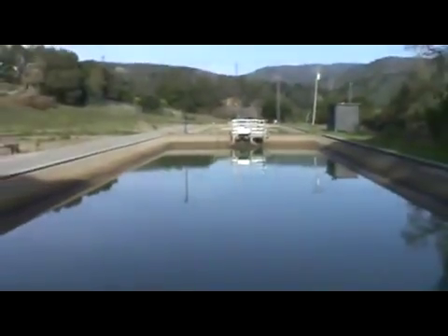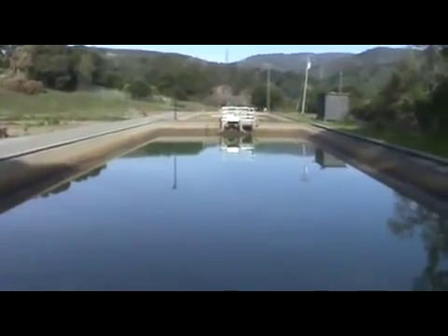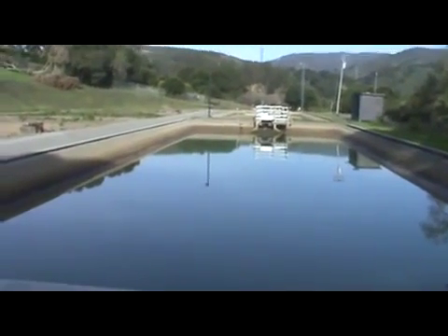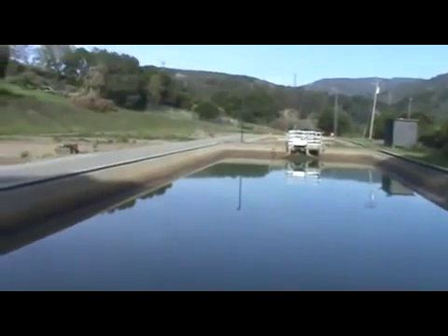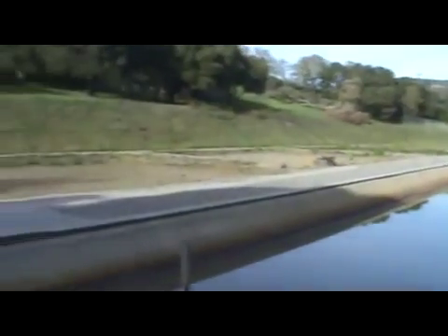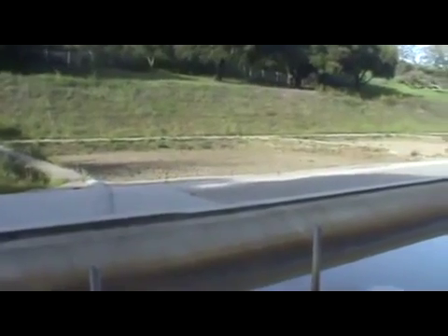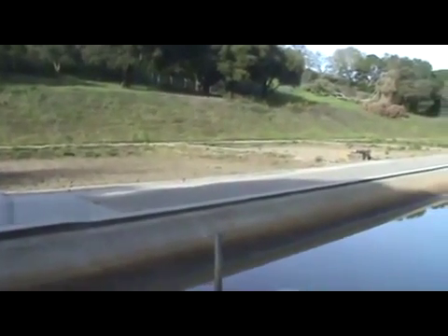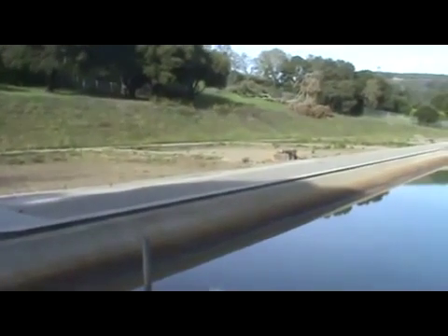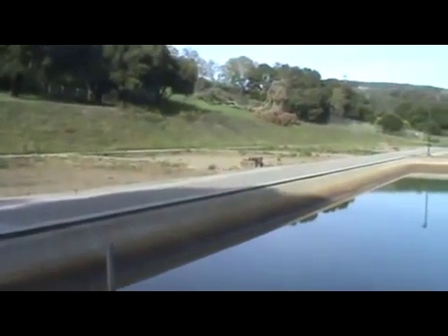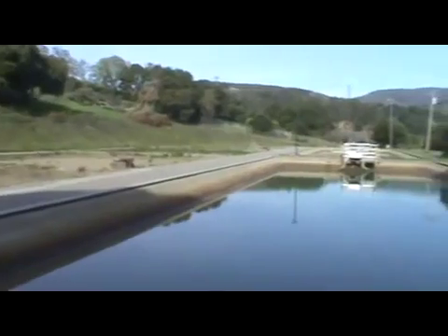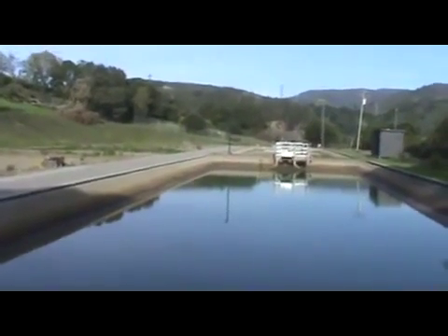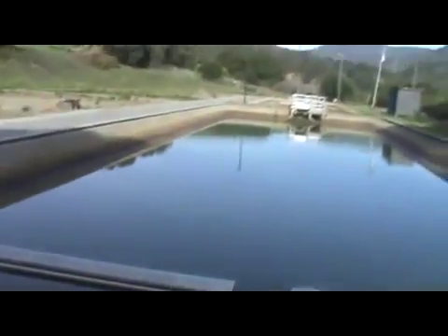It has a little bit of time to settle in these lagoons, and then on a timer, an arm scrapes the bottom, and sludge pumps underneath pump to these drying beds over here, which allow the water to settle down and the dirt and everything to dry. Once these get filled up, they get cleaned out and the dirt gets hauled away. So that's what happens once that water leaves the backwash process.